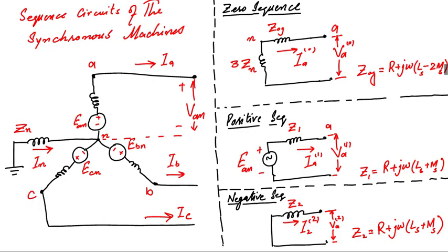As in previous case we have seen that zero sequence impedance of transmission line could be as high as 3 times of the positive sequence. But in case of generator, the zero sequence will be smaller than its positive and negative sequence impedances. So generator has smaller zero sequence and transmission line has much higher zero sequence impedance.